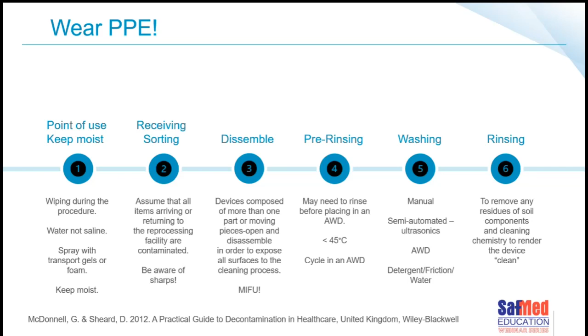In the washing phase now, it could be manual, it can be semi-automated, it could be a washer disinfector, it could be all of the above, based on the instructions for use. And of course, we need detergent, friction, and water. And ultimately, we need to rinse the device because we want to remove the residues of the soils as well as the residues of the cleaning chemistry to be able to render it as clean, or defined as clean.